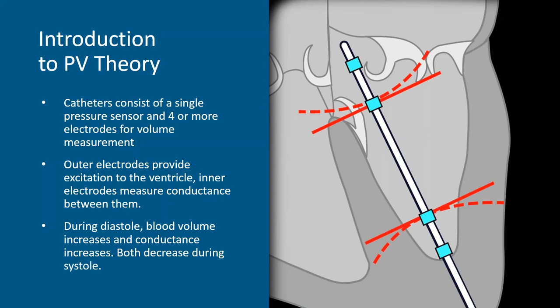So how do we go from conductance or resistance to volumes? Again, it's a relatively simple calculation. You can see on the left here a cross-section of the heart. This is a multi-electrode conductance catheter. The current is injected between the outer electrodes and the voltage drop is collected between successive pairs of electrodes. Those pairs essentially act like a cylindrical segment in the chamber, and if you have multiple segments, all those cylindrical segments are added up to give you a final volume.